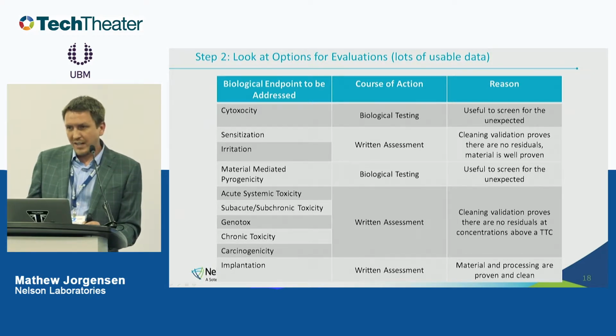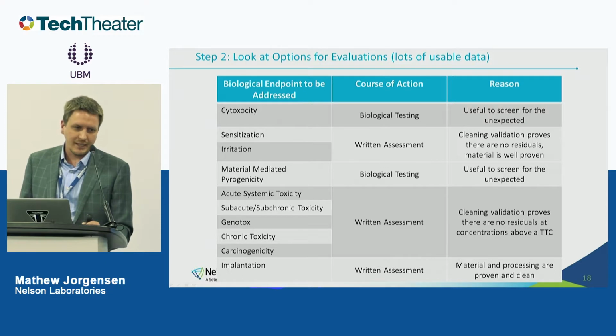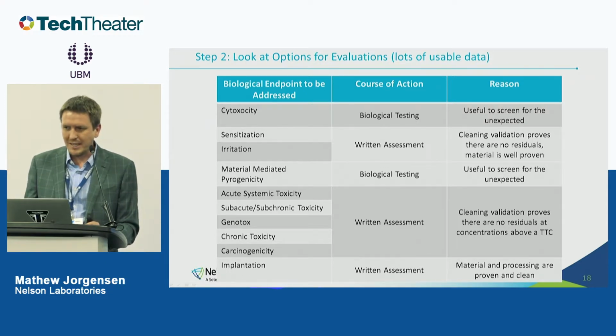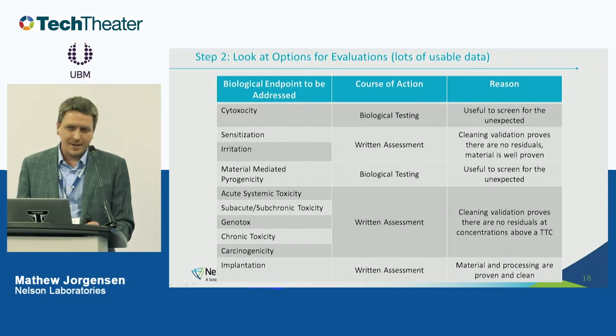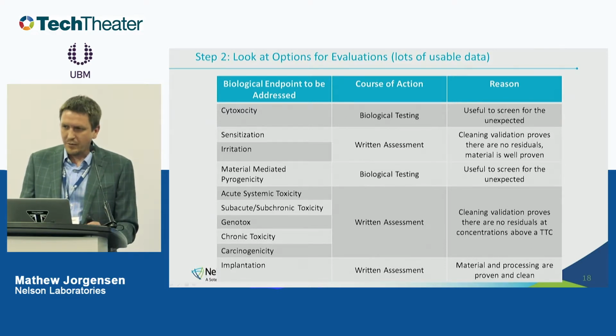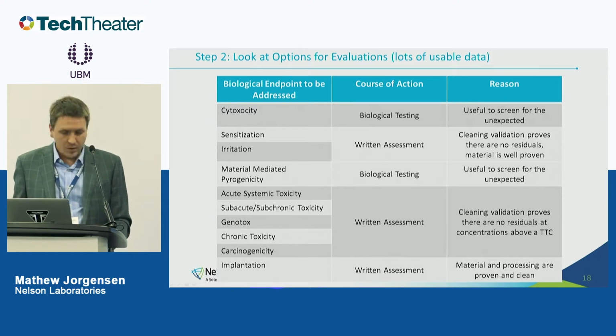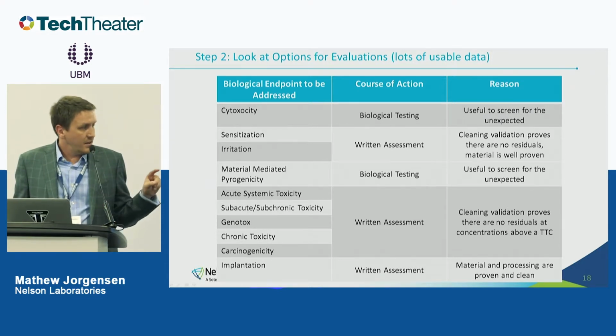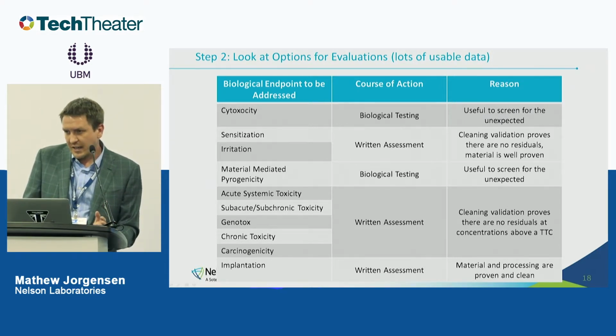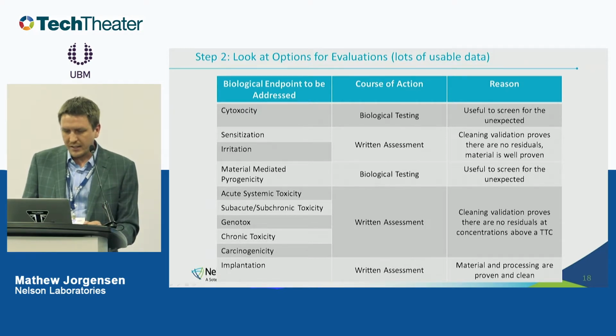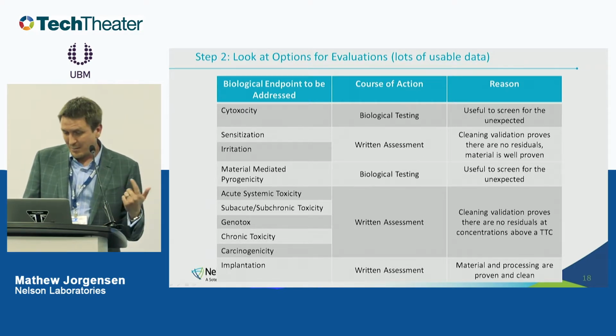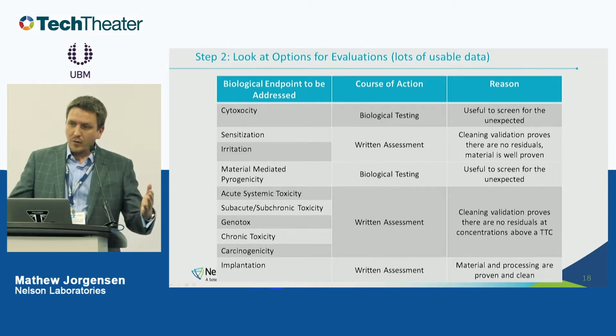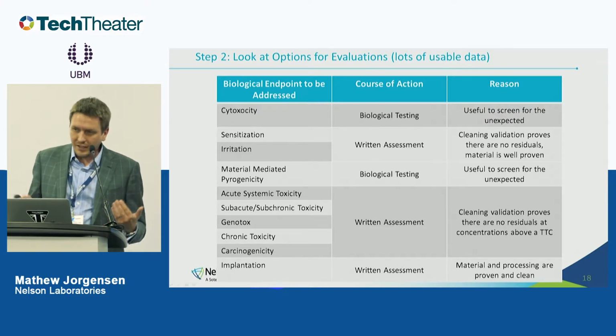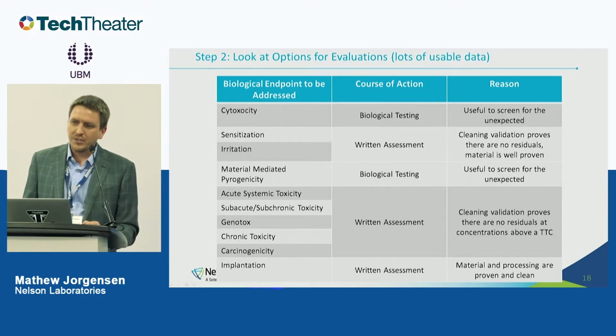But if your device is made out of a plastic material, if we're talking about a catheter set or some tubing set, even if it's clean, you probably are still going to need to do some testing, just because plastics are so ambiguous as to what they can release to the body. So in this case, they did have really great cleaning validation data, so we were able to limit their testing quite a lot just to the cytotoxicity and the material-mediated pyrogenicity. Of course, we have to review tons of cleaning validation data, but that's a lot less burdensome than running through the test.